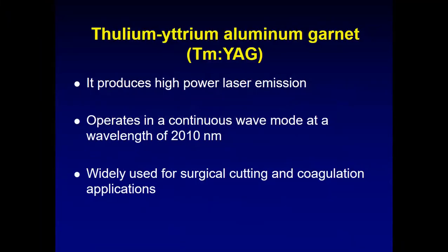So now a bit about the thulium YAG laser. This is a new laser as well, and it provides high power laser emission. Holmium had 2100 and it has 2010 nanometers, widely used for surgical cutting and coagulation. And now there is a comparison going on between holmium and thulium for stones as well.